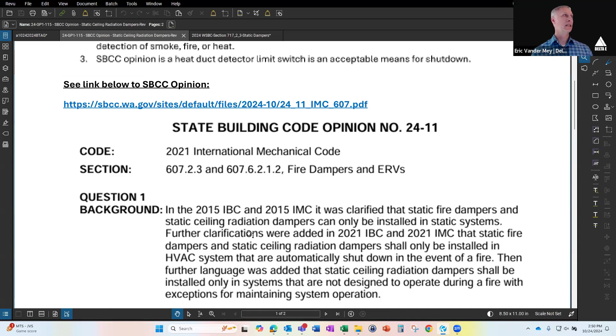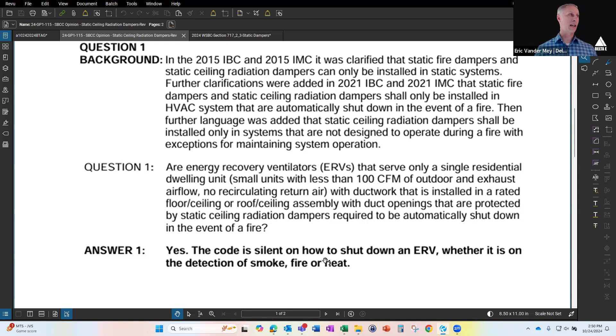The first question looked at by the council was, do you have to shut down? The answer was yes. The code is silent on how to shut down the ERV, whether on detection of smoke, fire, or heat. There is no clarity. The second question was, would it be acceptable to use this heat detector duct limit switch in the return of an ERV? That was said to be an acceptable means. They did not render an opinion on what that limit switch should be set to; that would be deferred to the AHJ.